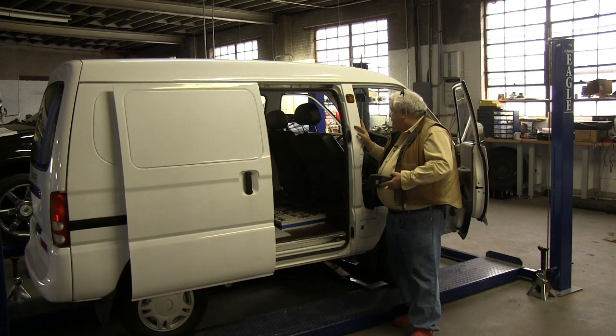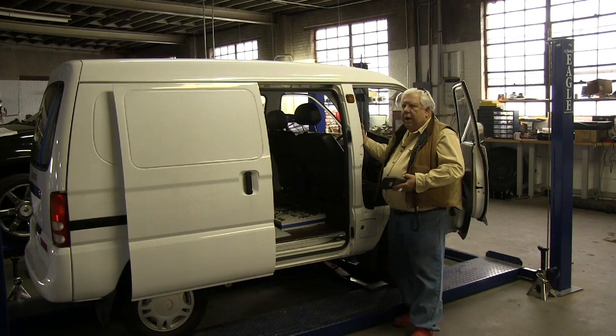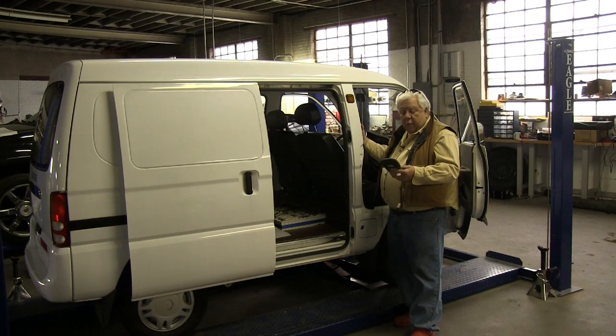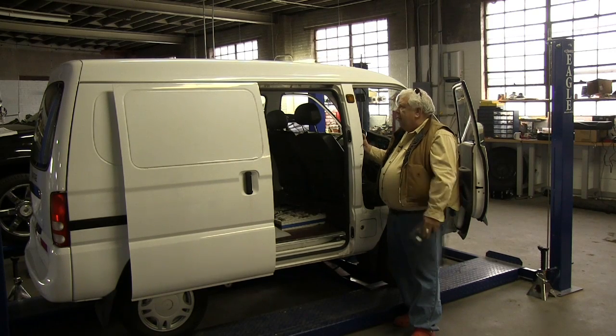So I pulled it out and checked the faults on this, and it had quite a history. I cleared the history, ran it a little bit, and I kept getting an over voltage cutoff fault. Let's talk about that a little bit.